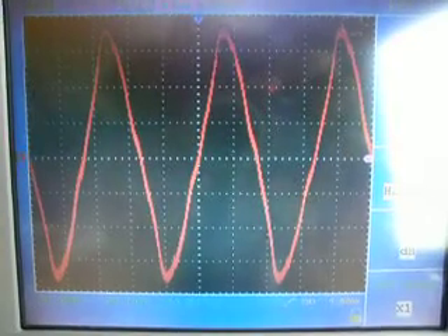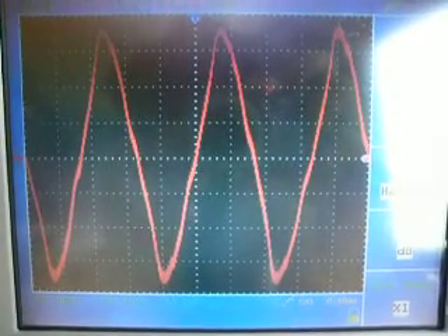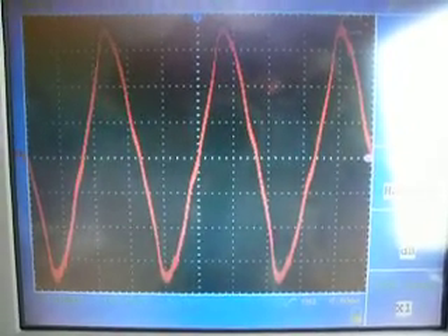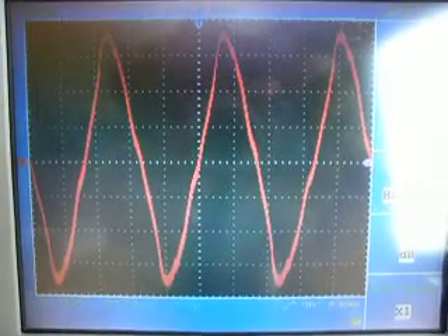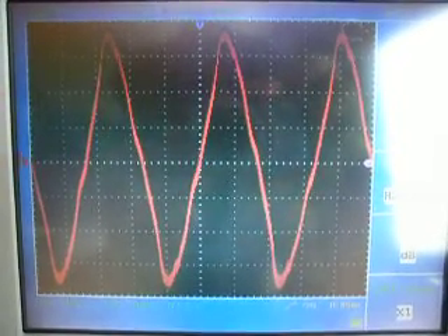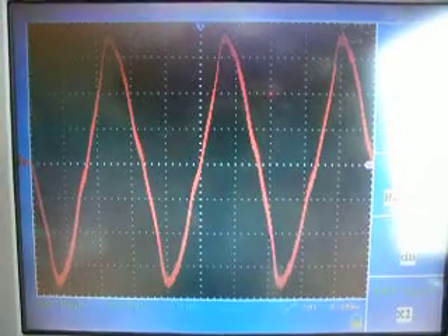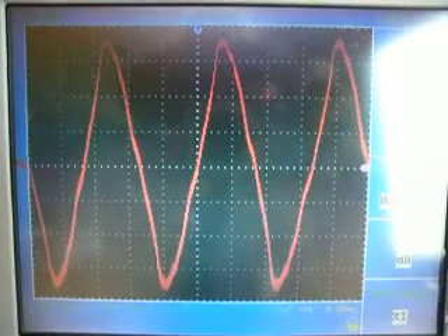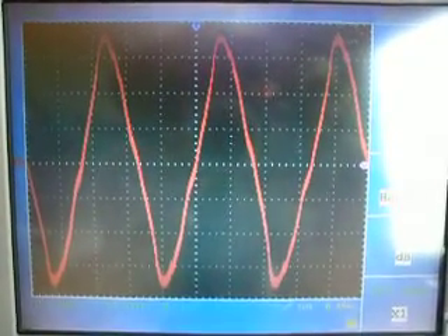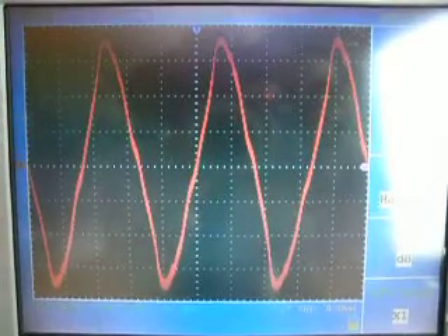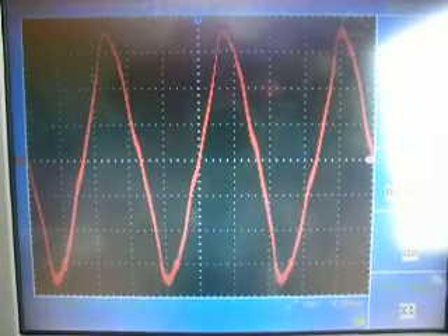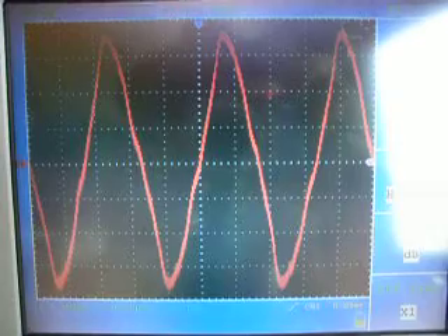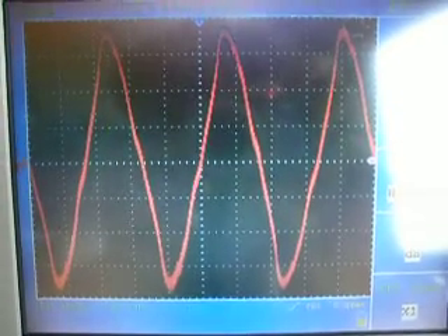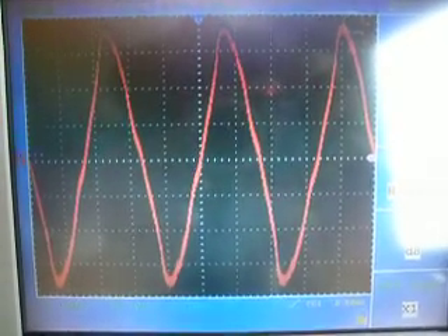For those who don't really understand what a grounding system is, it's actually the neutral connection of the utility transformer in the USA. This connection goes to every transformer neutral connection on the system, and that's why we have a voltage on it. So the ground is not actually at ground potential, it's actually at 4 volts AC peak to peak.